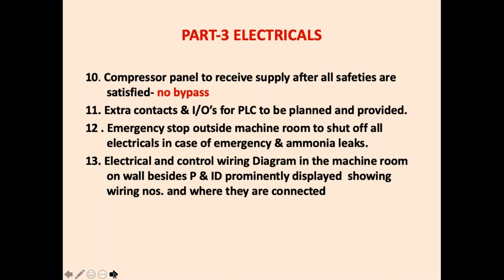And provide an electrical wiring diagram in addition to the P&ID diagram, and display it inside the machine room so that the operator is able to trace the wire, which wire is going where, and he is able to locate, if some bulb or some red lamp comes on, what is causing that. So electrical wiring diagrams and piping and instrumentation diagram should be displayed in a machine room. That is a very, very important suggestion.